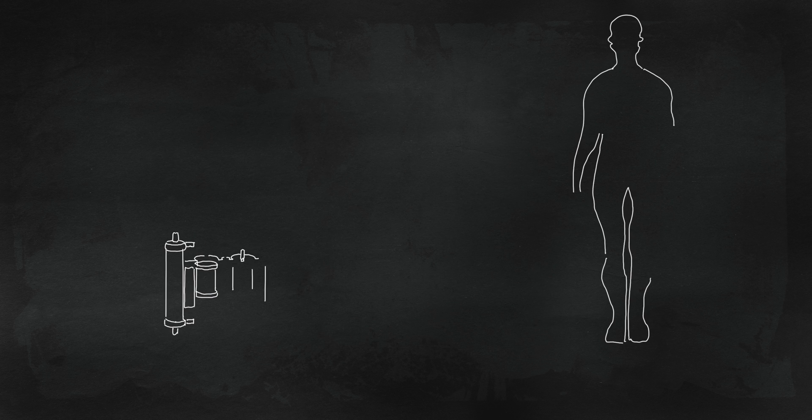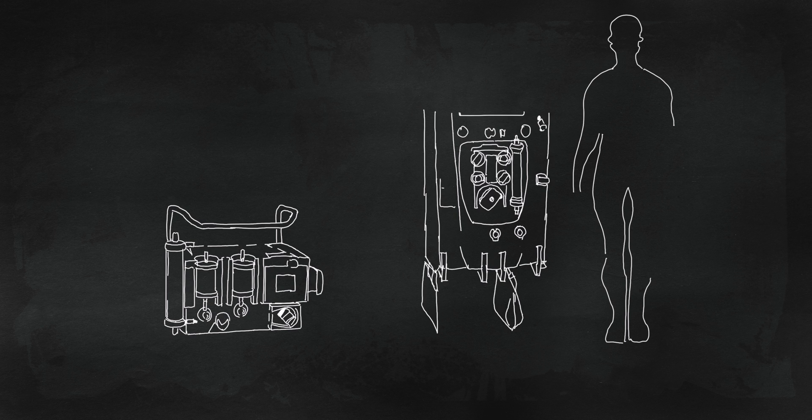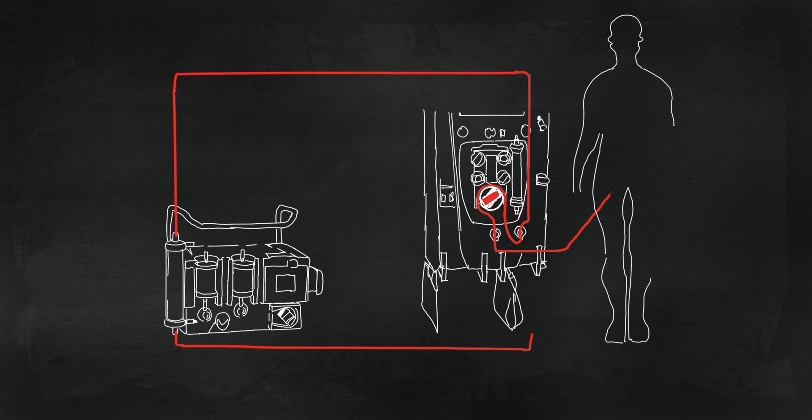Next, let's review the setup on the actual machine. There is the add-on MARS module, which works with the CRRT machine. The CRRT blood pump draws blood from the patient and sends it first to the MARS machine-hosted high-flux MARS flux dialyser, and then returns to patient.